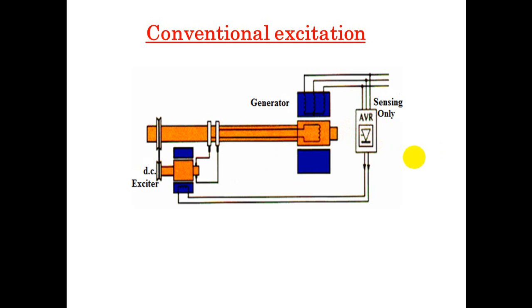The DC exciter needs current in its stator field winding to provide in turn the current in the main generator's rotor field winding to build power output. The exciter uses at start the remnant magnetic field of its own iron frame. It's like a small permanent magnet, which can provide at least a small current in its output.